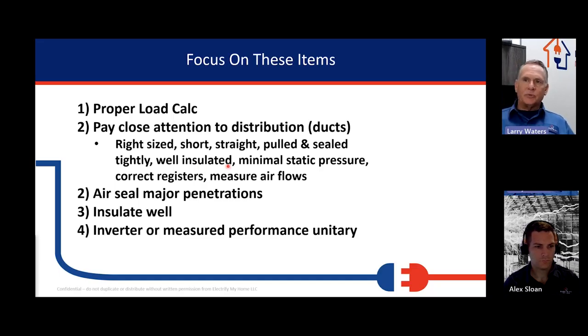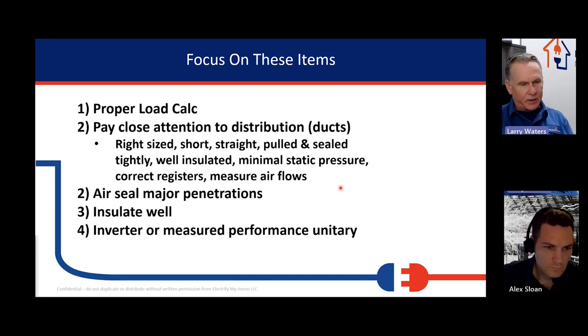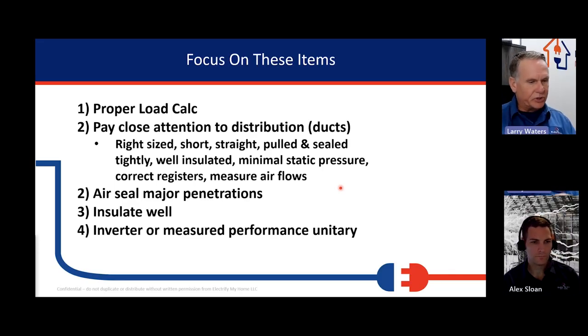Pay close attention to air distribution, the ductwork. They need to be sized right. When we're putting them in and resizing and redoing them in the attic space, if you have the ability to shorten up those duct runs, put the outlets on the inside of the house blowing out so we can shorten up the duct run, that reduces the thermal mass that's in the attic and it reduces the amount of heat we're going to pick up. So pulled tightly, put in straight, short as possible, well insulated, keep the static pressure low. Put some elbows on those turns when they go into the boots. Put some elbows on the 90-degree turns as they go through the attic. It's not that hard. It costs a little bit more, but you can charge for doing better work.